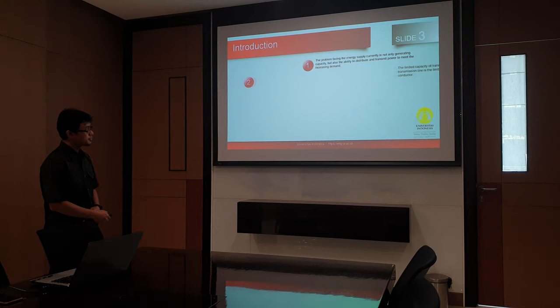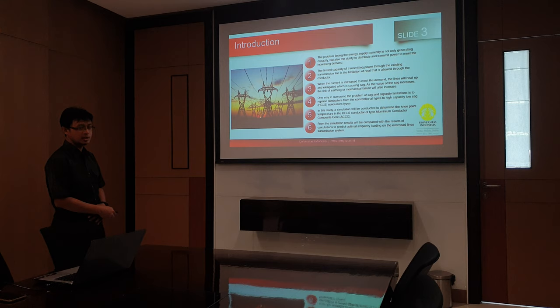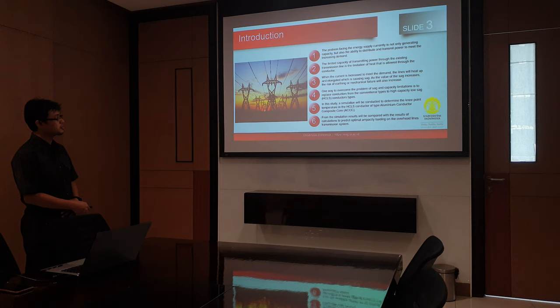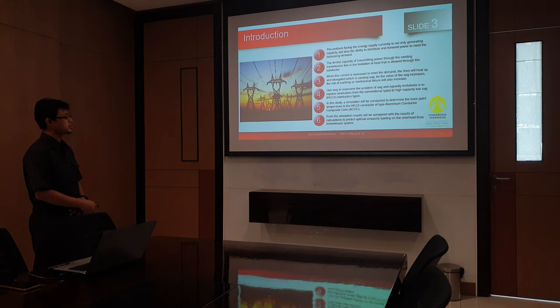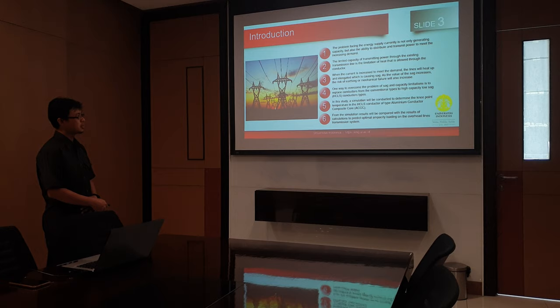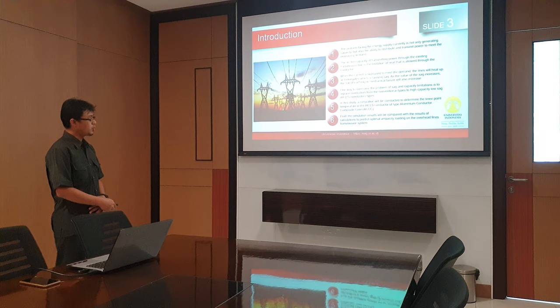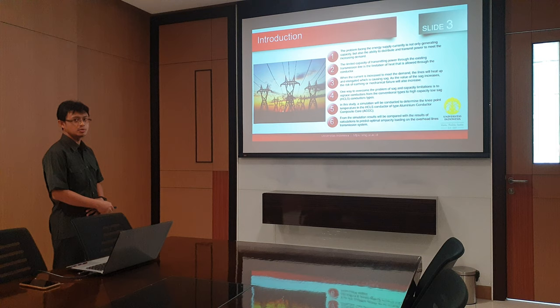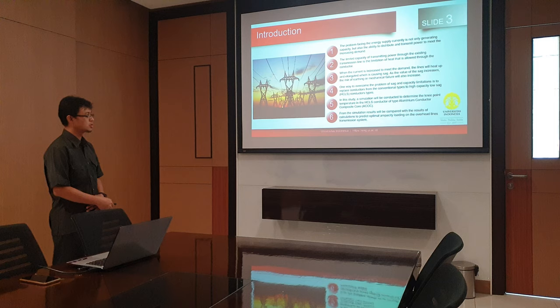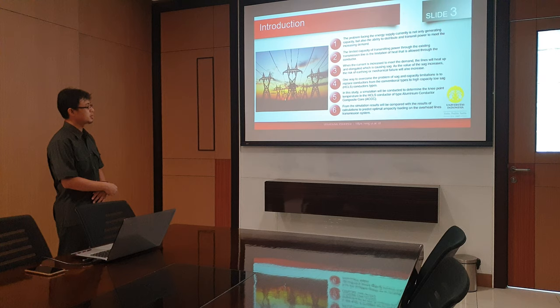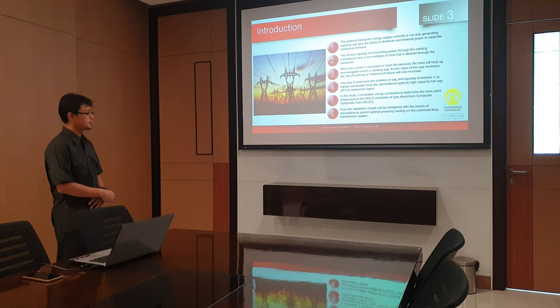Introduction. We know currently the problem facing the energy sector is not only the generating capacity, but also the ability to distribute and transmit the power to meet the increased demand. The limited capacity of transmitting power through the existing transmission line is the limitation of heat that is allowed through the conductor. One way to overcome the problem of sag and capacity limitation is re-conductoring — replacing the conductor from the existing conventional type to a high-capacity low-sag conductor.